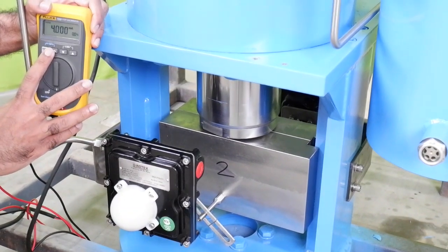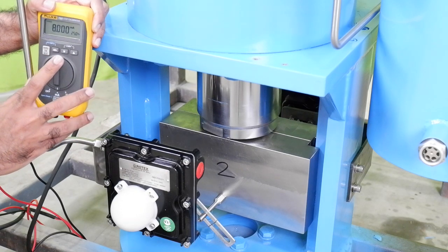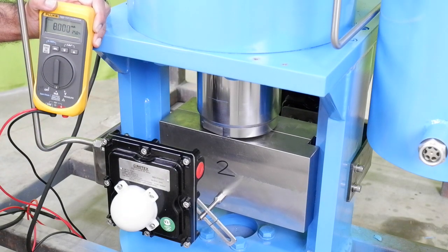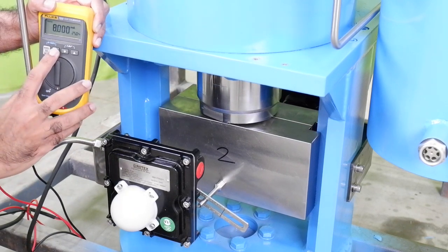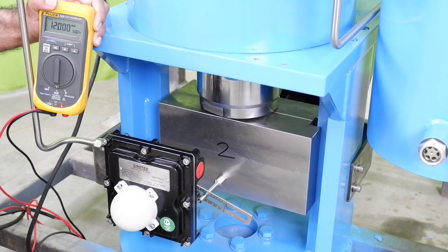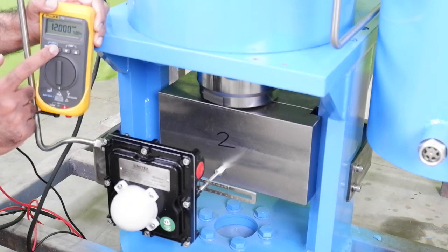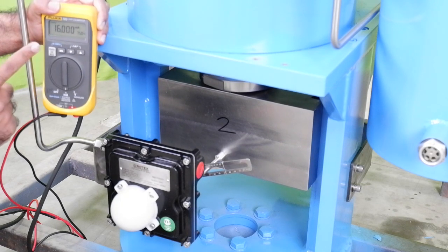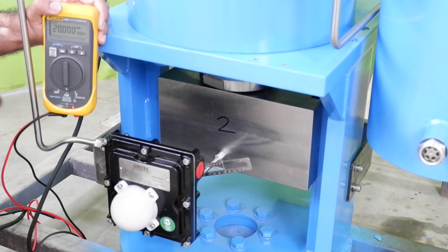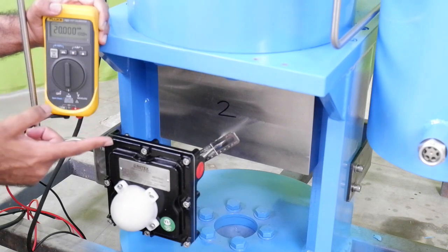Here the cylinder is in closed condition. So now we will open it by changing the set point. You will have to change it to remote mode. Now as soon as the signal is 25%, the valve has opened 25%. Now when signal is 50%, the valve has opened 50%. Now when the signal is 75%, the valve has opened 75%. And now for 20 milliampere, the valve is fully open.